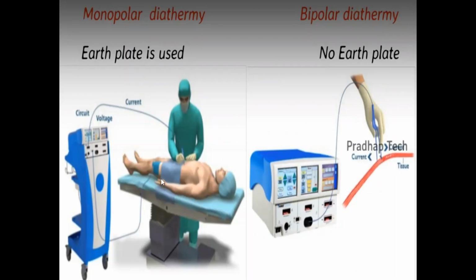Monopolar diathermy uses an earth plate. So you connect the wire, and the circuit completes in one loop. The electrical current is passed through the wire and comes to the monopolar diathermy probe. The heat is applied to the tissue to cut or coagulate, based on whether you're pressing yellow or blue. And then the current goes through the patient's body and is earthed via another cable that is connected to the machine. So it has to go through the patient's body. It uses the patient's body as a passage for current. This is why the earth plate is used.